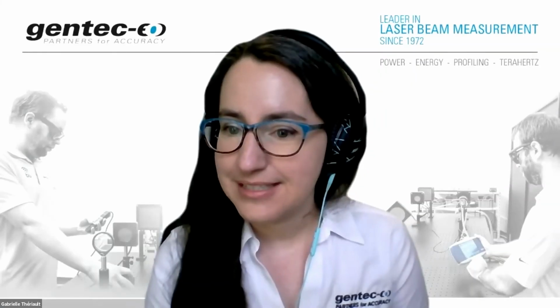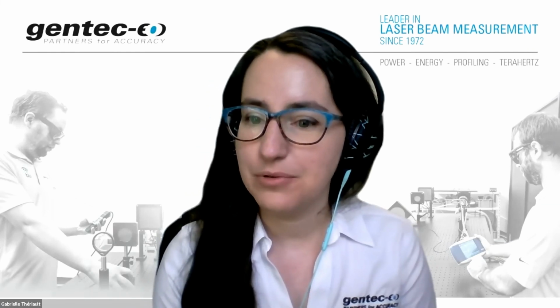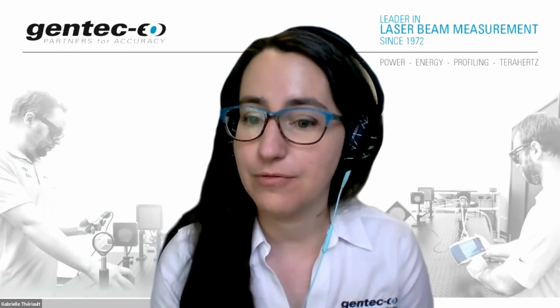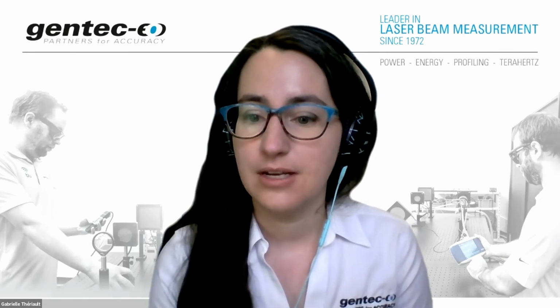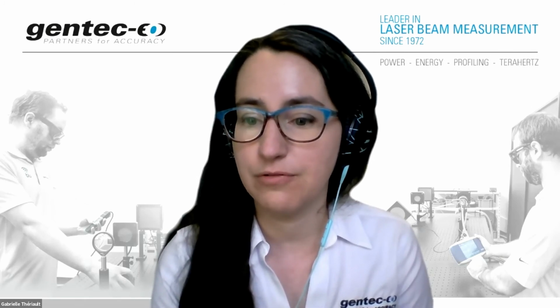Also from the chat, does a change in room temperature affect the detector performance in the case of pyroelectric detectors? Say an increase in room temperature from 22 degrees to 26 degrees. It's not expected to be that important because a pyroelectric detector, once again, will sense the variation of heat brought by the laser beam. So if your room temperature changes, it is not expected to impact the measurement accuracy significantly. From 22 to 26 with a pyroelectric detector, you should be safe.